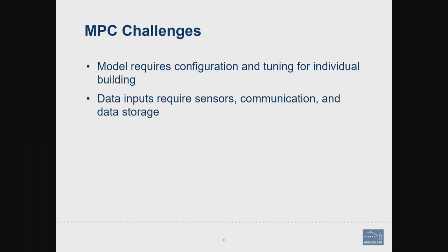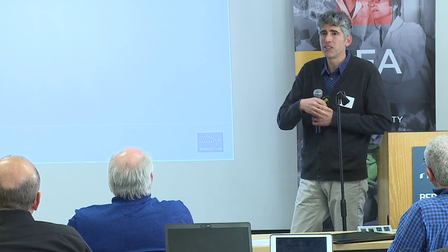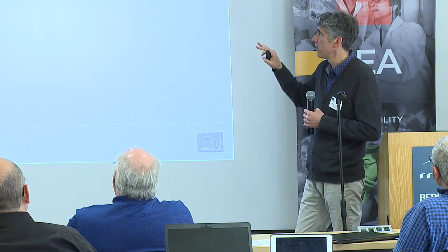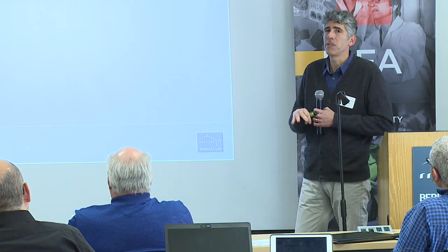So that all sounds great, but you guys have worked with real buildings, buildings never behave like you think they're going to. The convenience store, for instance, when we actually got there to install the model predictive control, the HVAC units weren't running properly. There were 2 rooftop units used for space conditioning. One was carrying all the load, the other one was carrying almost none of the load, balancing problems. So that's one issue with model predictive control, is that even if you have all these smarts, the underlying, the basic systems have to be working properly.